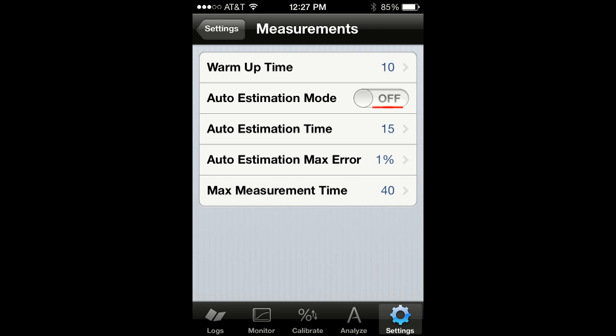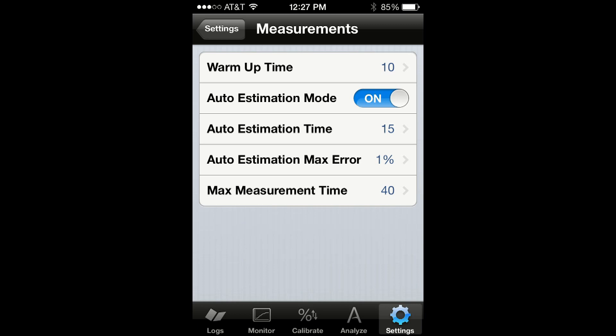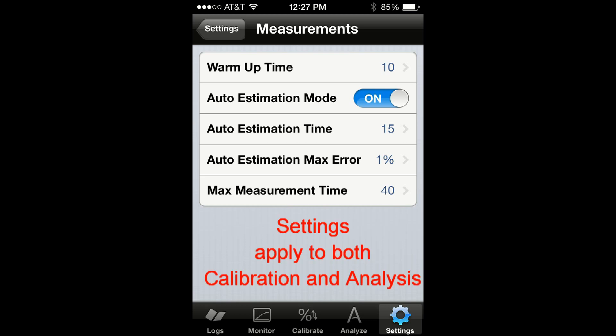If you disable auto-estimation mode, the time it will take to complete a measurement will be the value you assign to the max measurement time. But if you enable auto-estimation mode, the measurement might complete much sooner. This is because our proprietary auto-estimation algorithm determines when the measured value is stable enough to be considered valid. You can customize the auto-estimation algorithm by programming the length of the auto-estimation window and the maximum acceptance percentage error of the sensor output voltage being measured. Please note that the measurement settings apply to both the analysis and the calibration measurements.